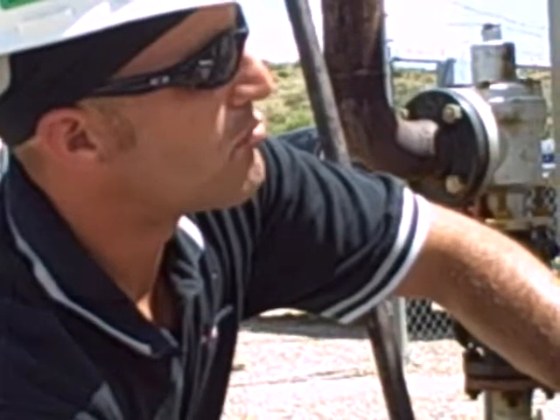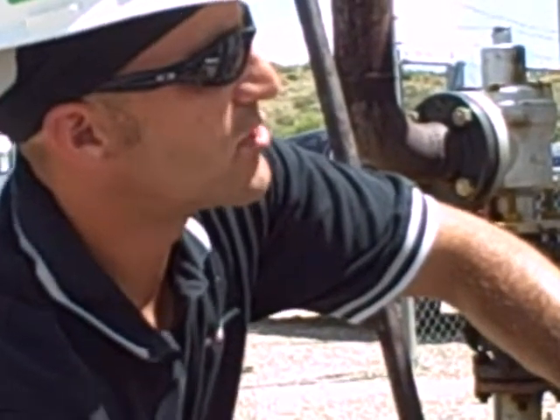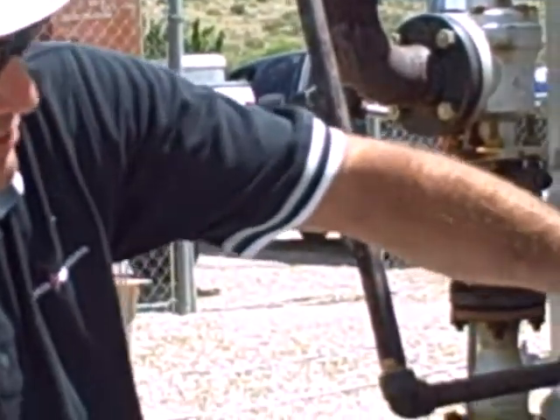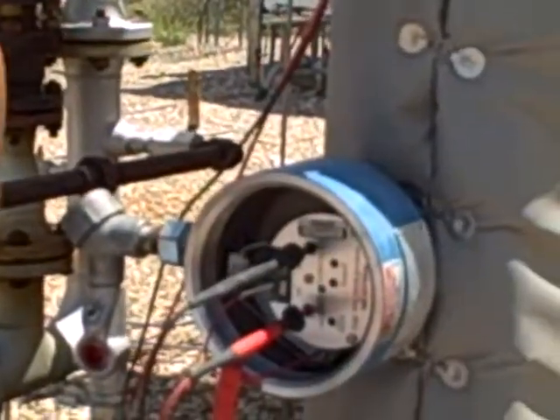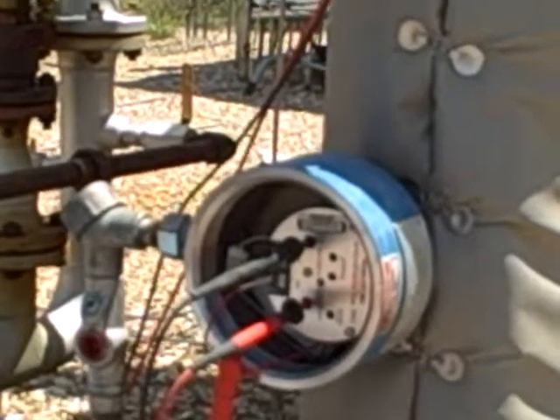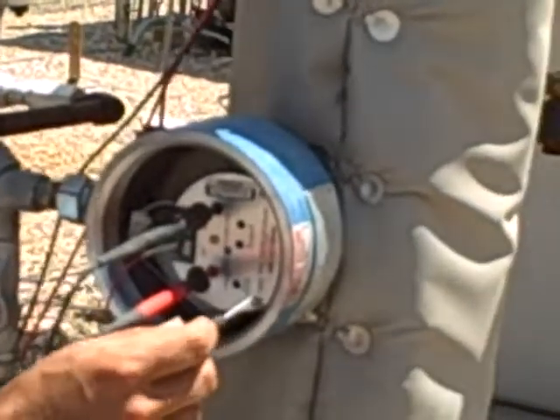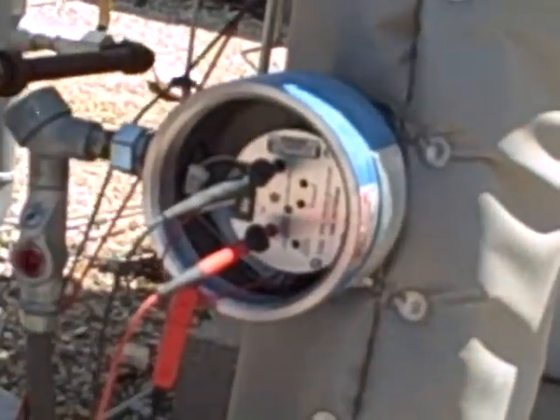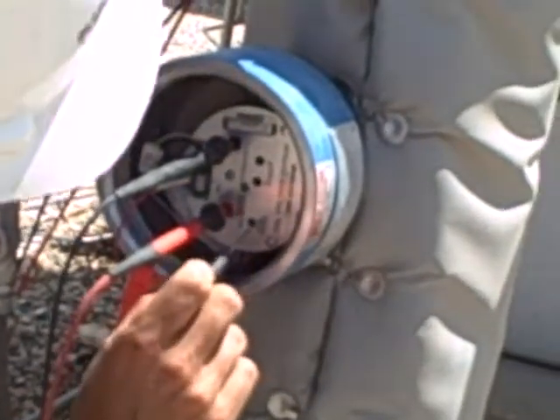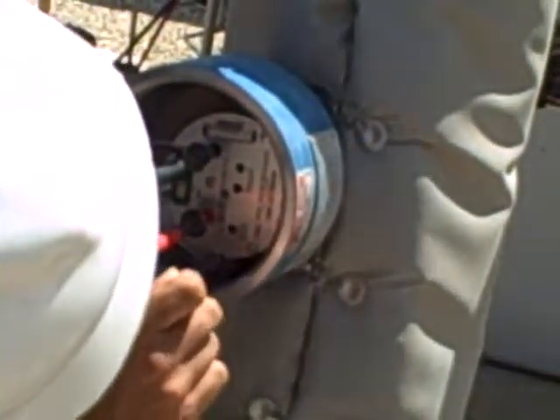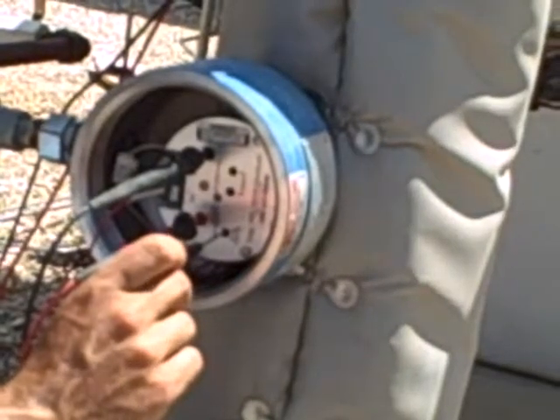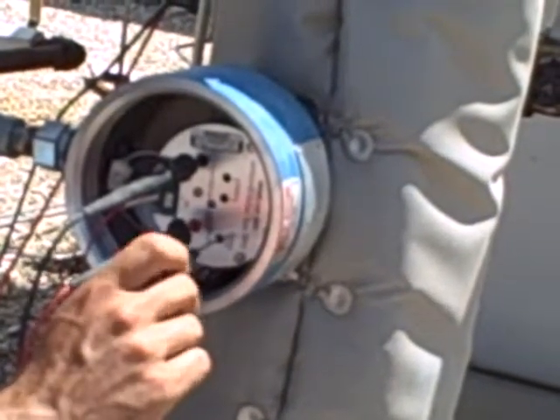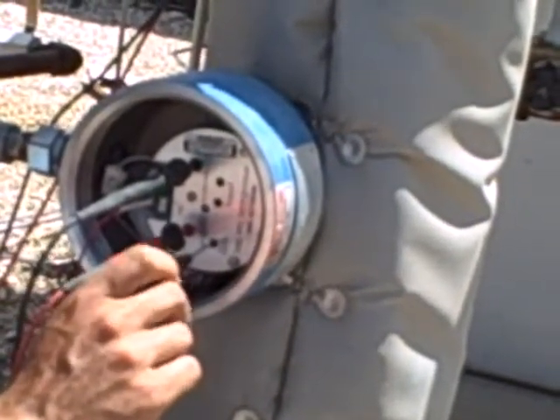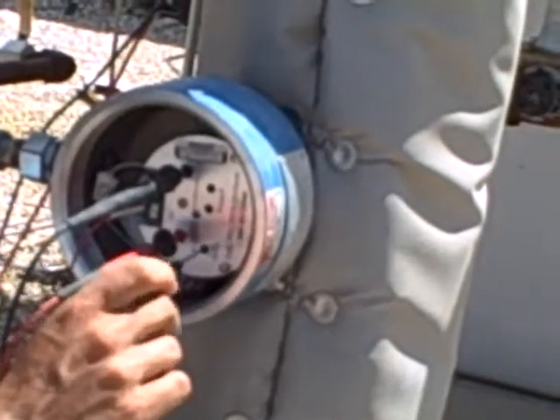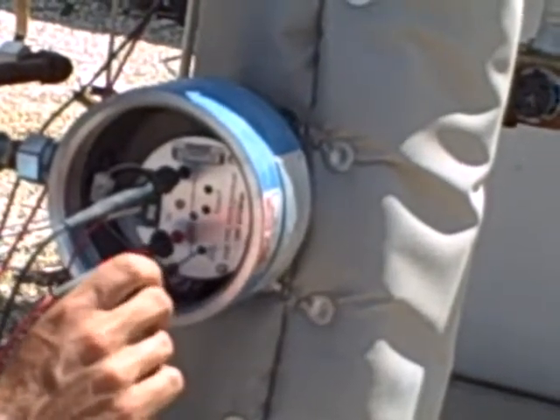Right there I got it at 0.152 volts, which is plus or minus 3%, so I'm within my range. I'm going to go ahead then and switch my toggle switch to reference, check my voltage DC, and it's at 5.32. I need to get that down to 5. So I'll go on the output span, and I'll adjust that down to 5 volts.